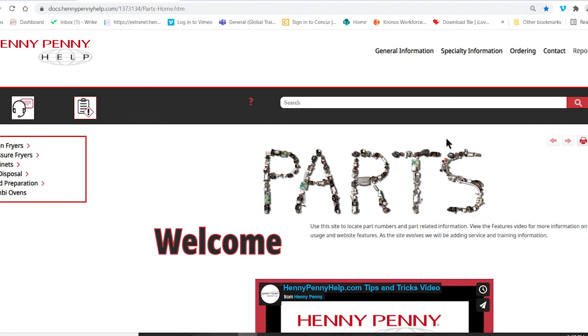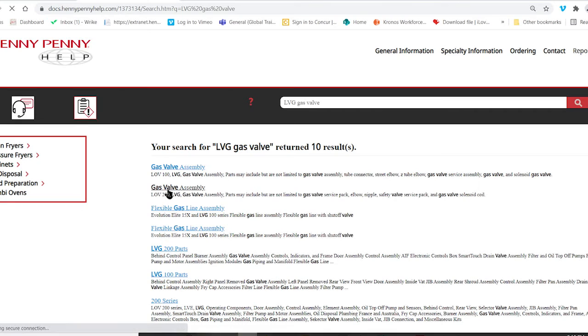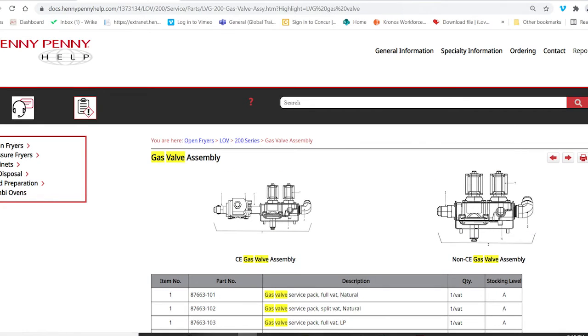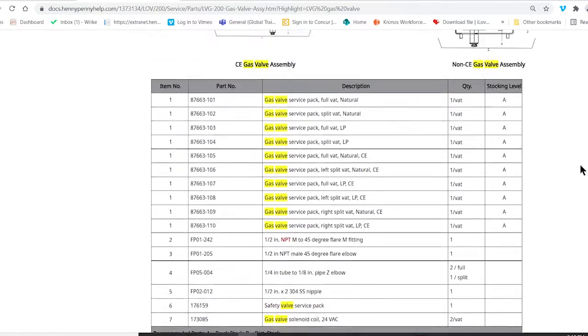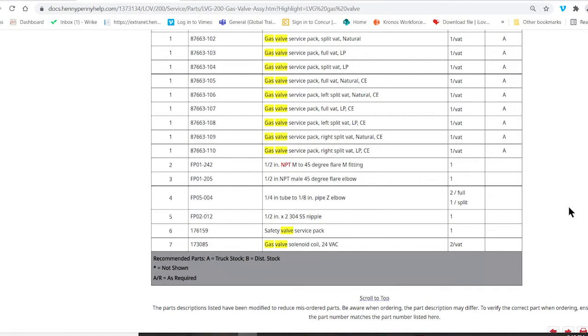I'm going to share screen because I want to show you where you can go to hennypennyhelp.com, and if you're needing these components, you can get the part numbers. From there, you can type in the model, LVG, and we know it's a gas valve. We'll click on search. We can see gas valve 200 series. We'll click on that, and it's going to pull up, and we can look and find different parts, different components. If the solenoid is bad, it's a 24-volt AC coil on it. So that's a part number you could use for it.